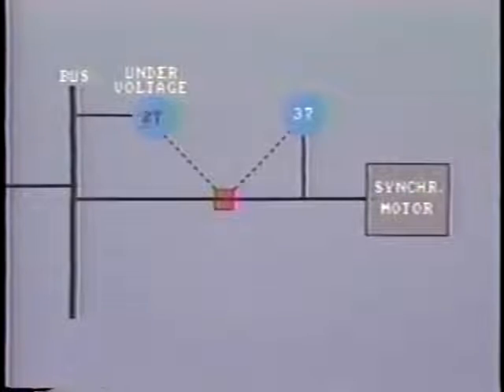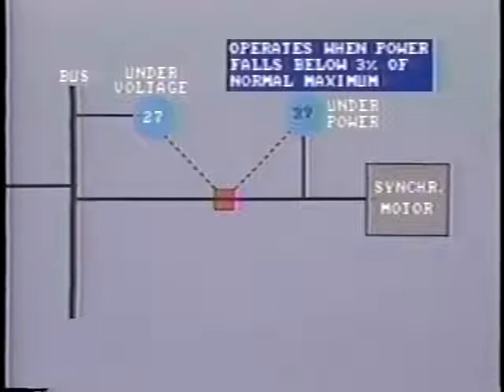As you would expect, synchronous motors are fitted with undervoltage relays so as to prevent rapid restart if loss of voltage occurs. This is the same as in induction motors. Additional protection for this condition is sometimes provided by an underpower relay, 37. This relay measures power being fed into the synchronous motor, and it is usually set to operate when power falls below 3% of normal maximum operation. That is, close to zero.